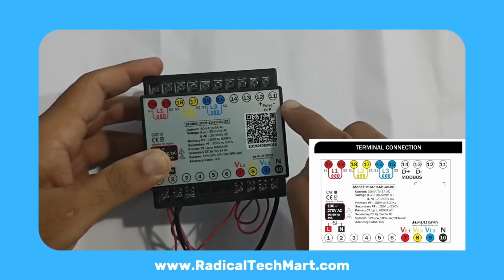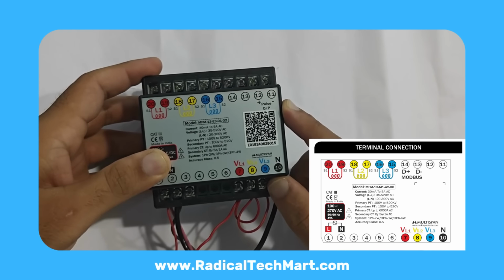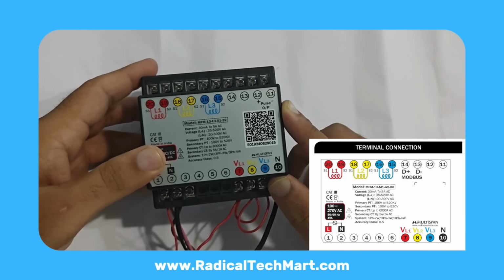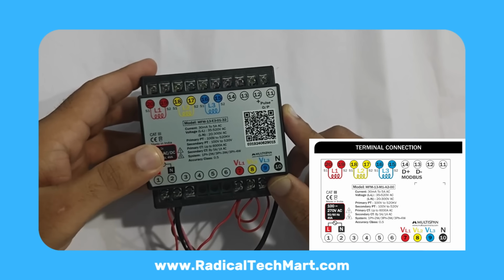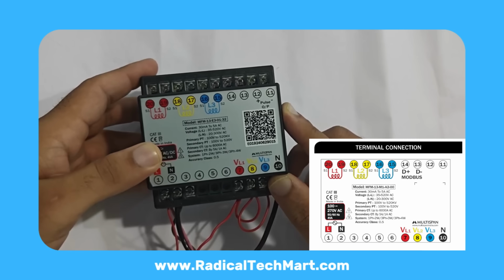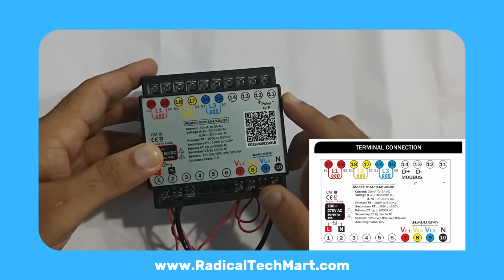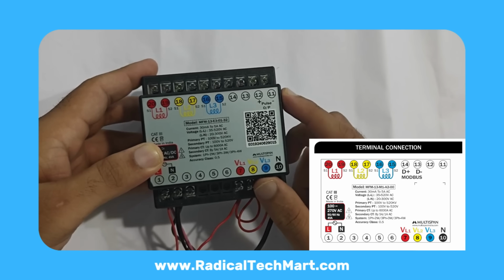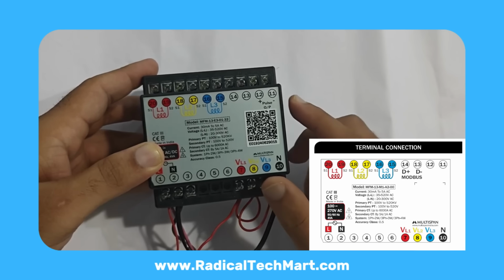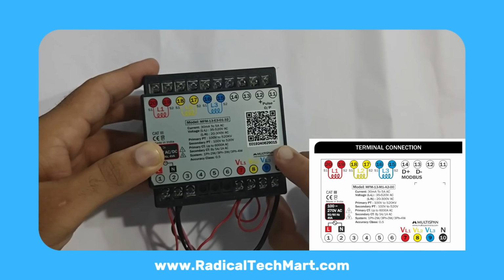Now for pulse output. Terminals 12 and 11 are pulse output terminals. You can use this pulse output in your PLC or HMI to monitor how much kWh is increasing over time. Basically, every pulse will represent a certain amount of energy. We'll see how to set that later.